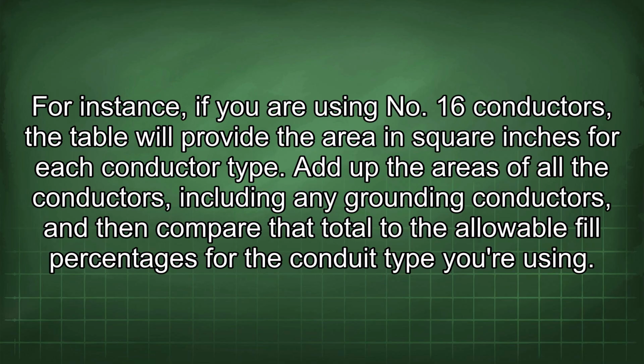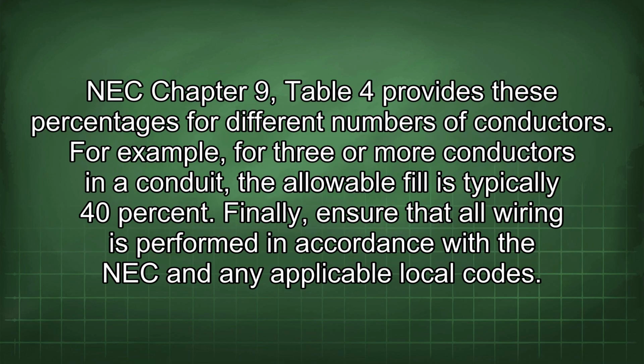For instance, if you are using No. 16 conductors, the table will provide the area in square inches for each conductor type. Add up the areas of all the conductors, including any grounding conductors, and then compare that total to the allowable fill percentages for the conduit type you are using. NEC Chapter 9 Table 4 provides these percentages for different numbers of conductors. For example, for 3 or more conductors in a conduit, the allowable fill is typically 40%.